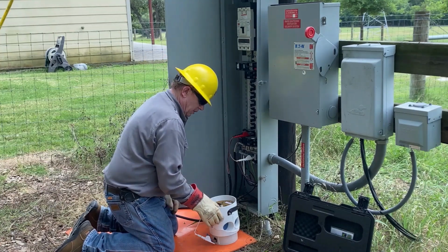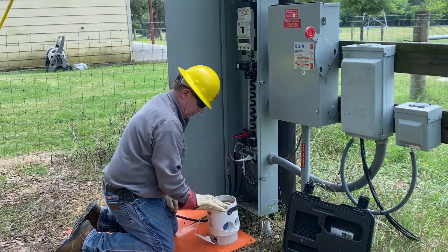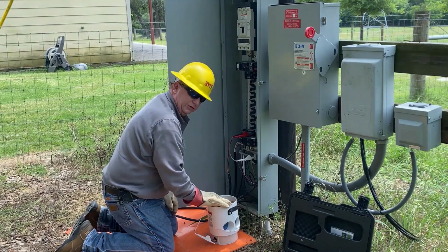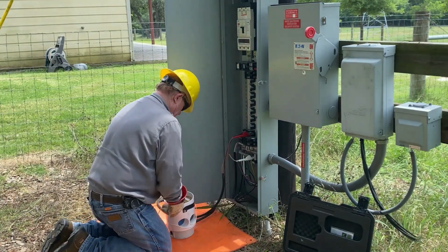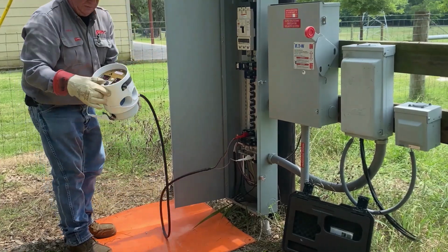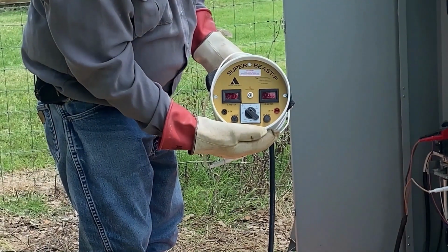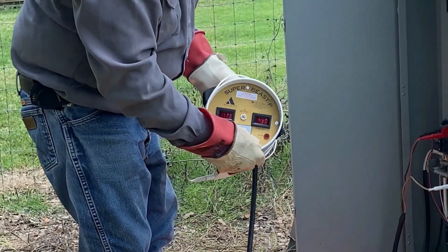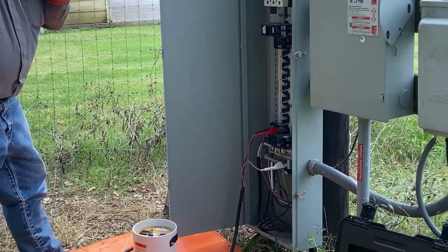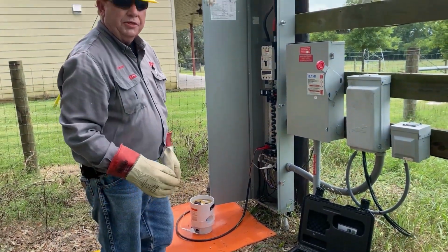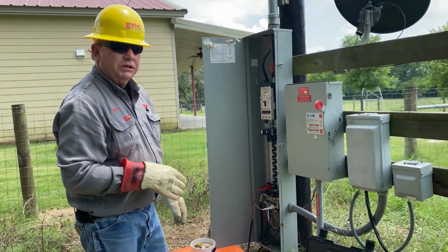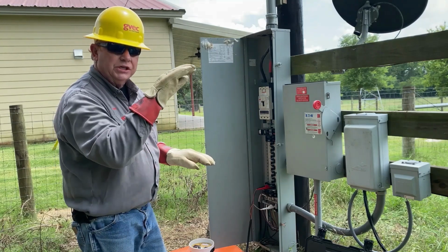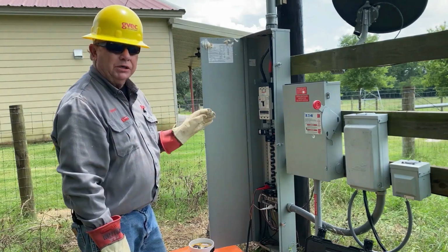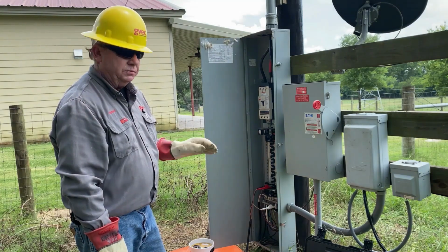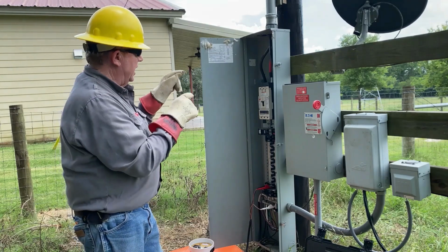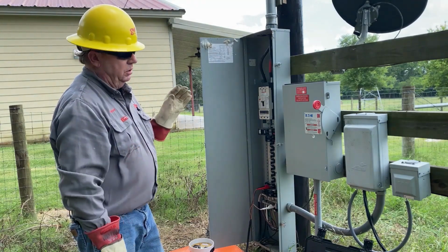Right now the Super Beast says the voltage is 122 and 122. We'll put on a 23 amp load and let it start cooking. Right now we have the 23 amp on one side, and our voltage has fallen to 113 and risen to 130. We're going to let that cook and monitor with thermal, and we should be able to see the hot joint. We'll be using a voltmeter, trying to find out where our loss is at.